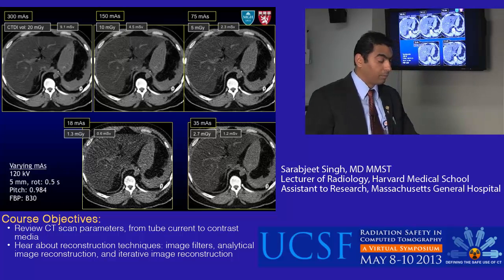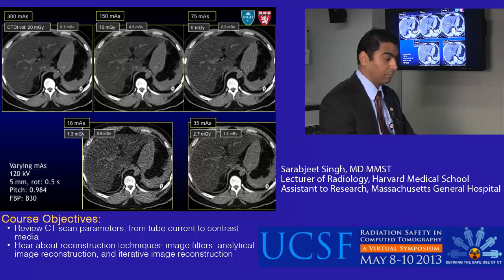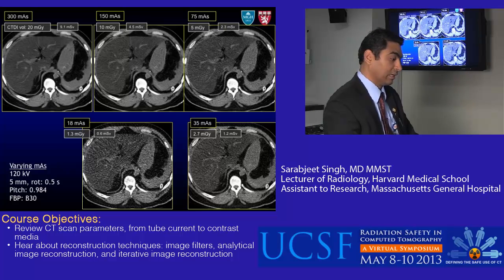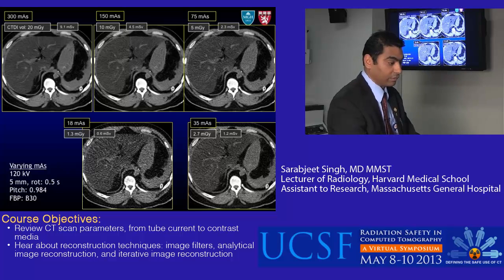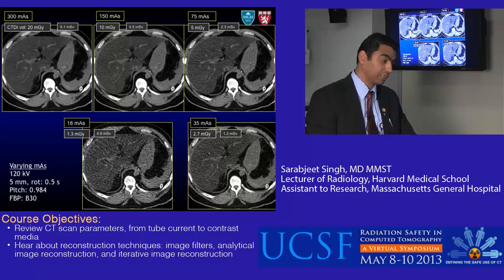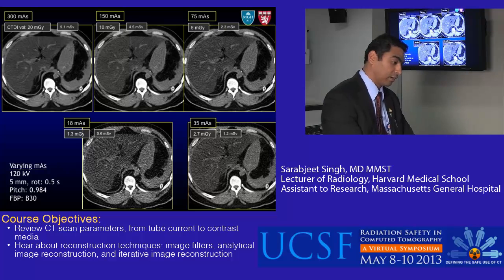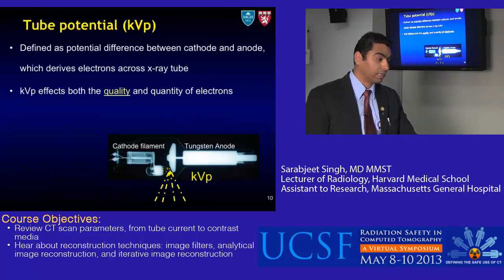Knowing mA is very important because as we lower mA, image noise increases and dose falls down linearly. For example, if we drop from 150 to 75 mA, the image noise goes up. When we lower mA, the quantity of electrons from the tube decreases, and so does the number of photons — that's why we have higher noise in the image.